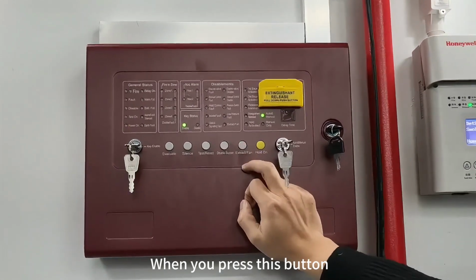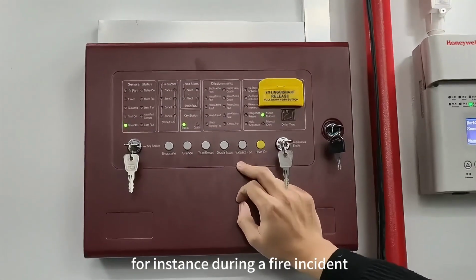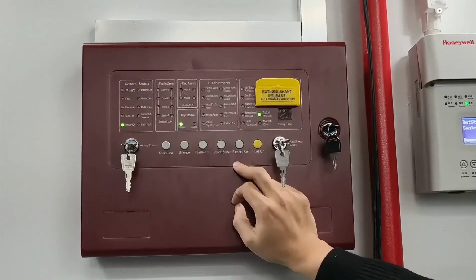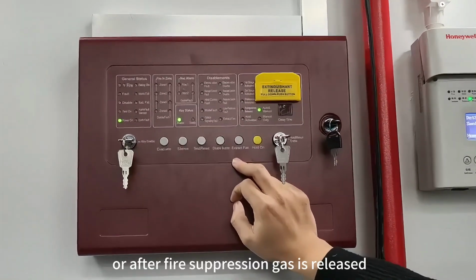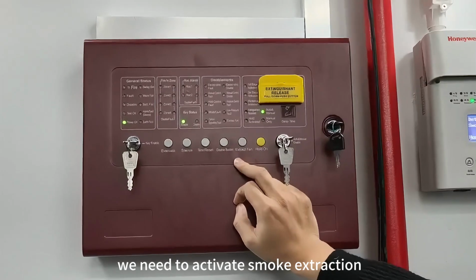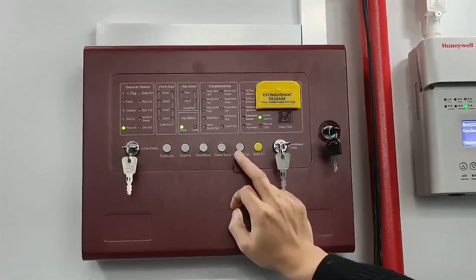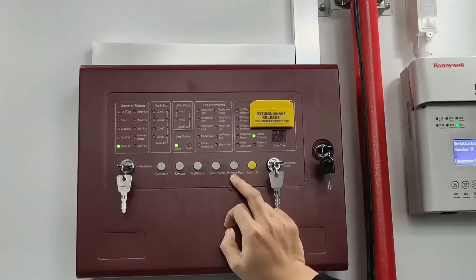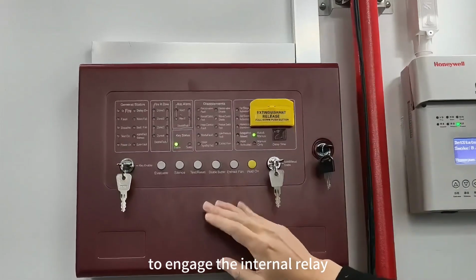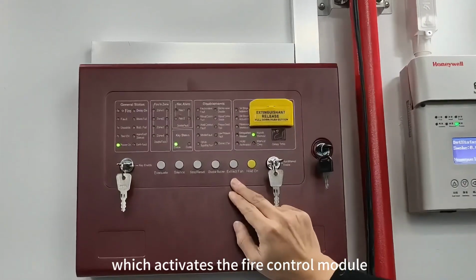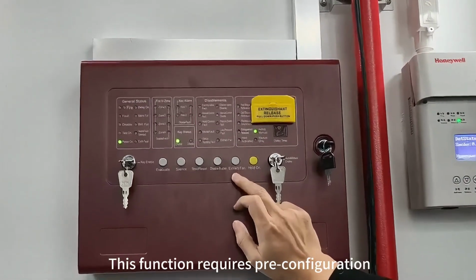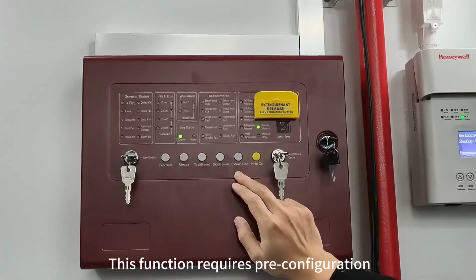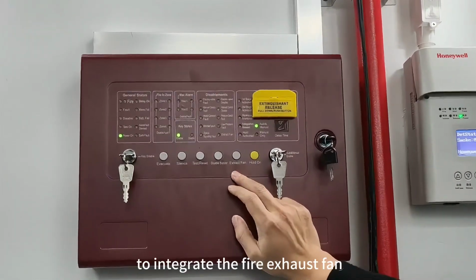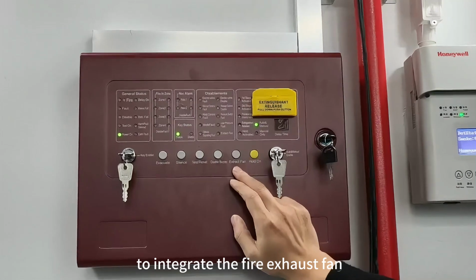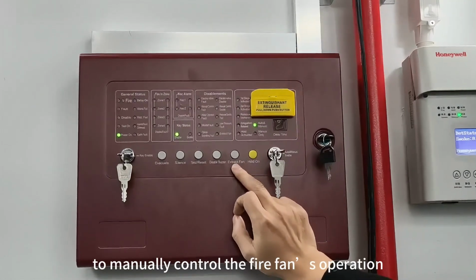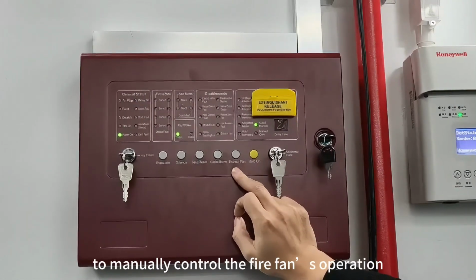When you press this button, for instance during a fire incident where heavy smoke is generated, or after fire suppression gas is released, we need to activate smoke extraction or gas ventilation by pressing this button. It engages the internal relay, which activates the fire control module. This function requires pre-configuration on the system. To integrate the fire exhaust fan, the button serves as a switch to manually control the fire fan's operation.